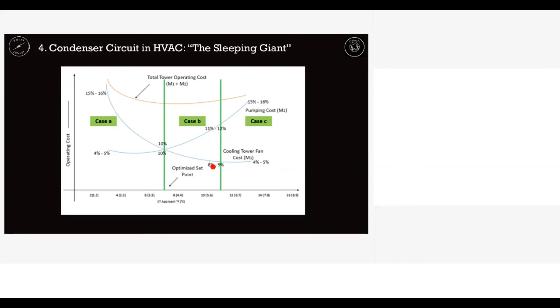the condenser pumping energy was somewhere around 5000. There are two cooling towers operating at 50 hertz, and the total is somewhere around this mark. In 2020, we installed a new cooling tower and shut down the first cooling tower, and only two cooling towers were operating. In the condenser circuit, the pumping energy was reduced because of the lower cooling tower approach we got from this new cooling tower. That does not mean all three are running. Only two cooling towers are running. The older one did not operate. At the same time, the pumping energy also came down. So this is how we save energy from the condenser circuit.